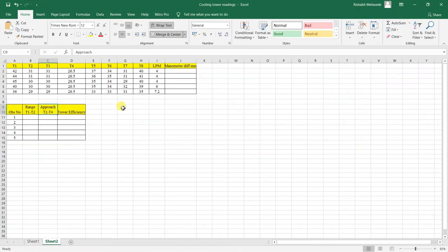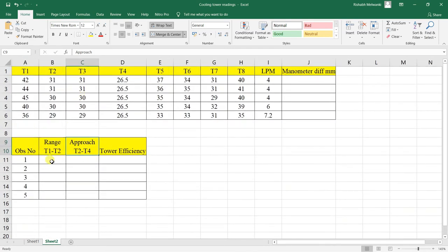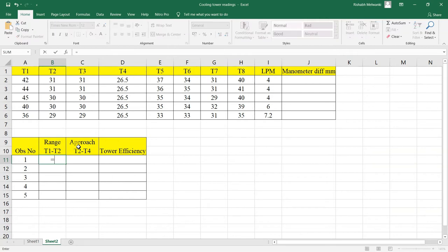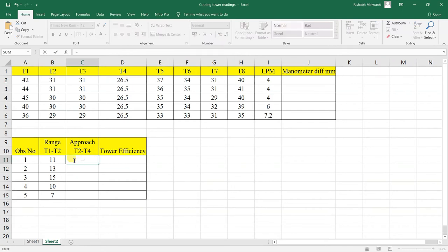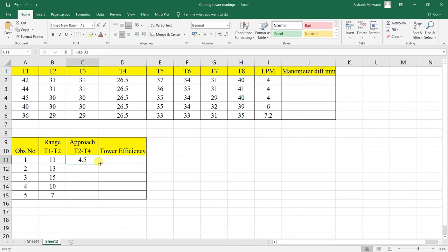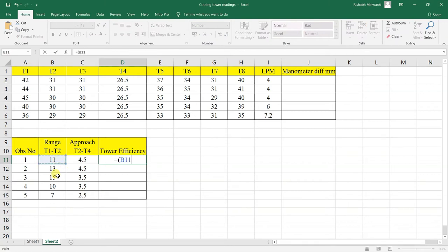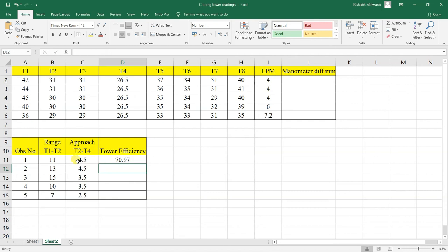We can do the calculations easily in Excel. Range is T1 minus T2, so we enter the formula and drag it to get all range values. Approach equals T2 minus T4. Tower efficiency equals range divided by (range plus approach), multiplied by 100.